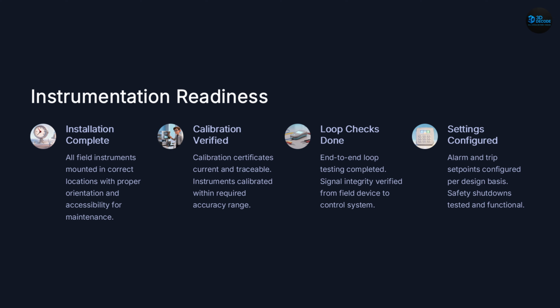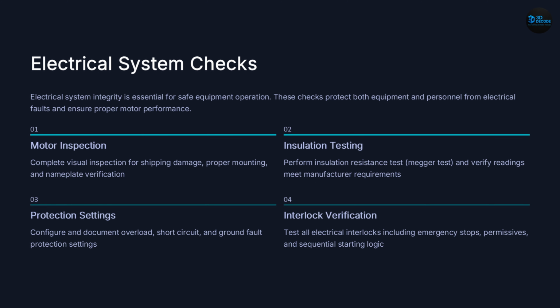Next comes loop checks. Signals must travel correctly from the field device to the control system. Without signal integrity, testing data becomes meaningless. And finally, alarm and trip settings. Configured, verified, tested, because protective functions must work before the equipment enters service. Remember this: bad instrumentation creates bad decisions, and bad decisions create commissioning delays. Next, electrical system checks.